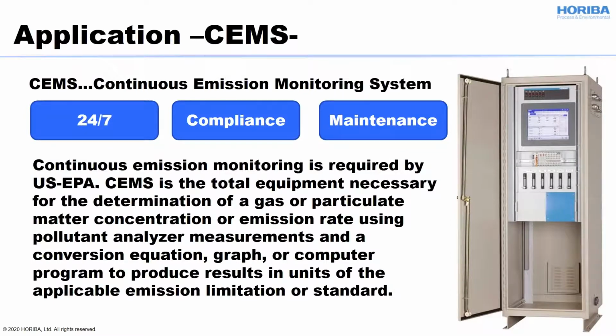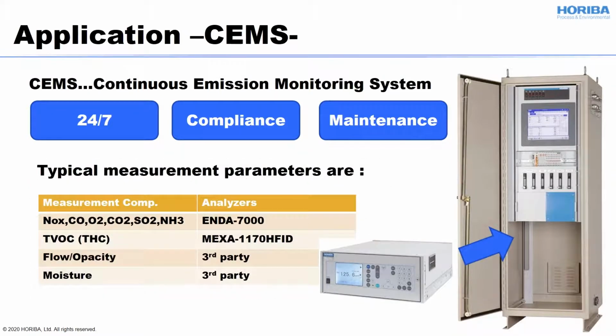Okay, let's talk about the application. CEMS, which is Continuous Emission Monitoring System, is required by US EPA. CEMS is the total equipment necessary for the determination of a gas or particulate matter concentration or emission rate using pollutant analyzer measurements and a conversion equation, graph or computer program to produce results in units of the applicable emission limitation or standard. That's the definition from US EPA for CEMS. CEMS requires measuring the emission gas from the plant to maintain compliance. So it measures the gas 24/7.